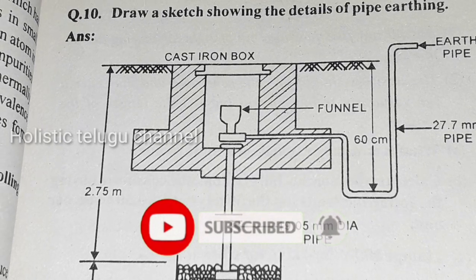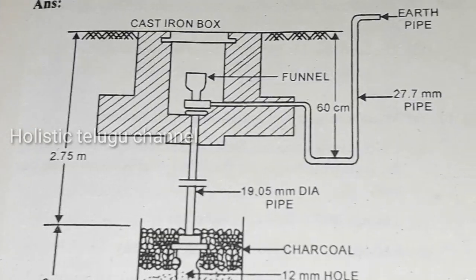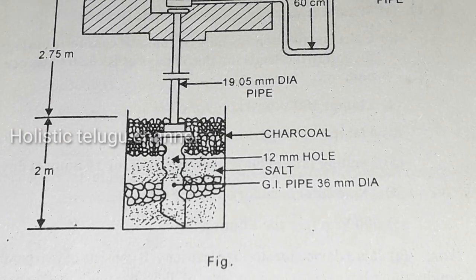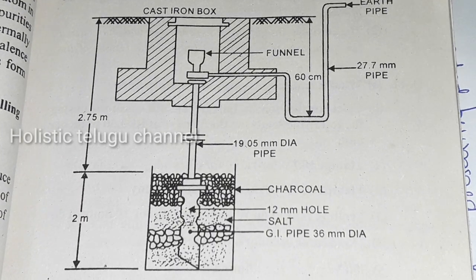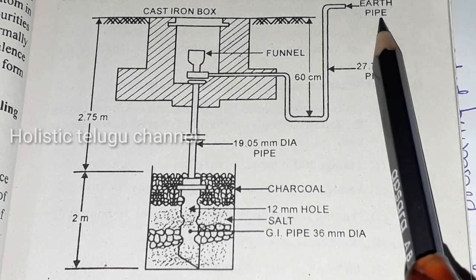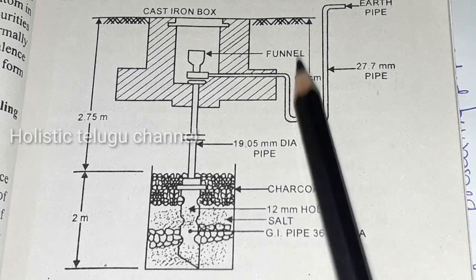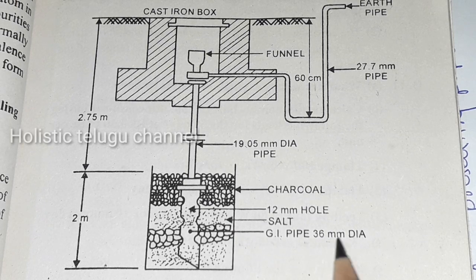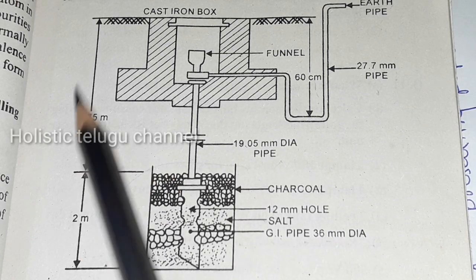Next question: draw the sketch of pipe earthing. In the pipe earthing diagram: a cast iron box is placed at the surface, followed by an earth pipe. Key dimensions include a 60 cm distance, 19.05 mm, charcoal, a 12 mm hole with salt, a GI pipe of 36 mm diameter extending 2 meters deep, and an overall depth of 2.75 meters. Students should be able to draw and label the pipe earthing diagram.